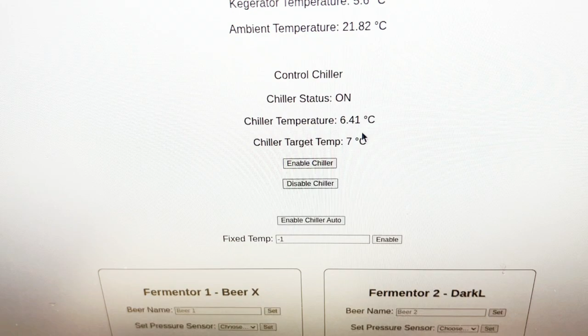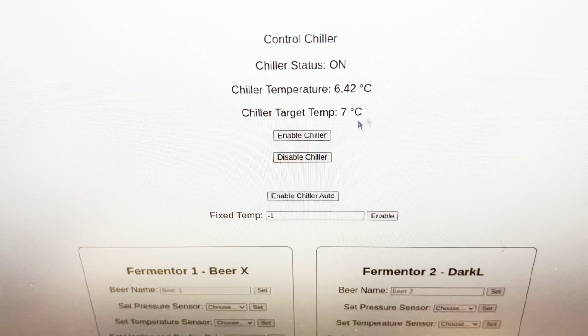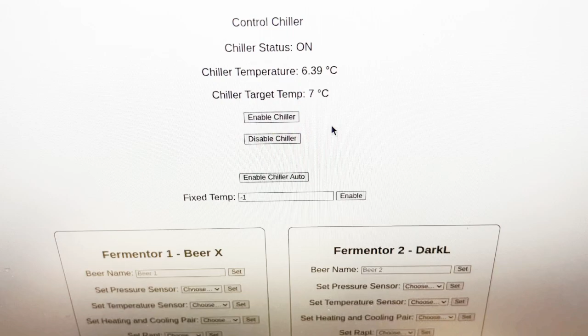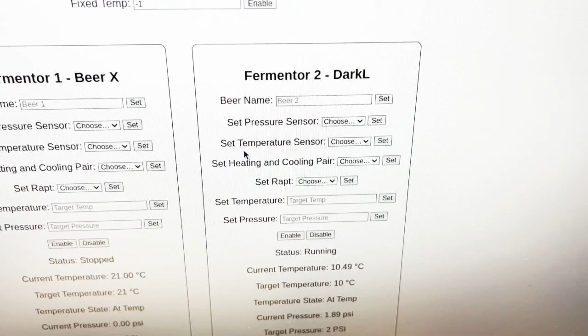Chiller temperature is currently at 6 degrees. The target tracks below the lowest fermentation temperature, so you don't have to spend a lot of energy chilling your glycol down to like -1 if you don't need to. The dark lager's been put in what is called fermenter 2. I'm fermenting at around 10 degrees - it's currently at 10.5, and it controls within half a degree.